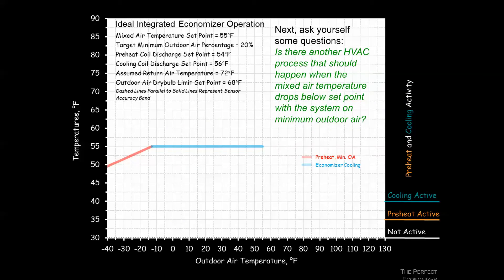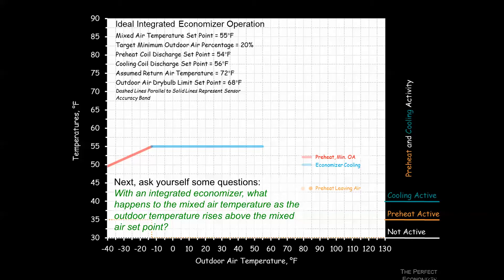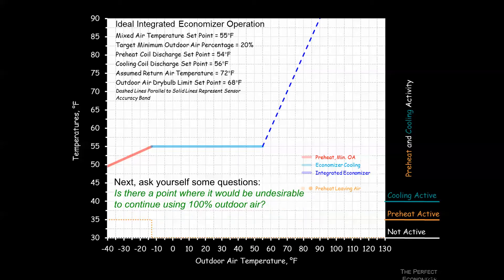When we can't meet 55 degrees at those cold temperatures, a preheat coil may come on. On the right side — when it's hotter than 55 degrees outside — the mixed air equals outside air, and in an integrated economizer cycle we continue using outside air even as cooling begins. The economizer high limit lockout is set at 68 degrees, where the profile changes shape.